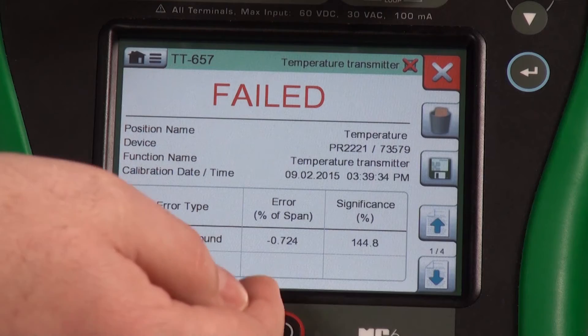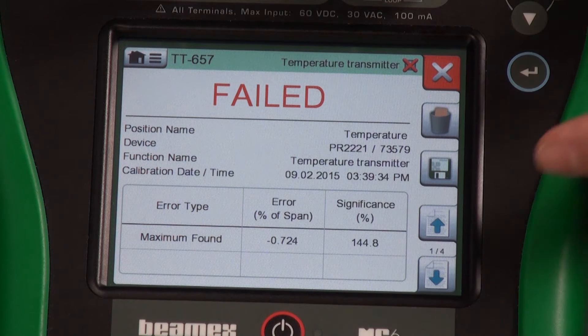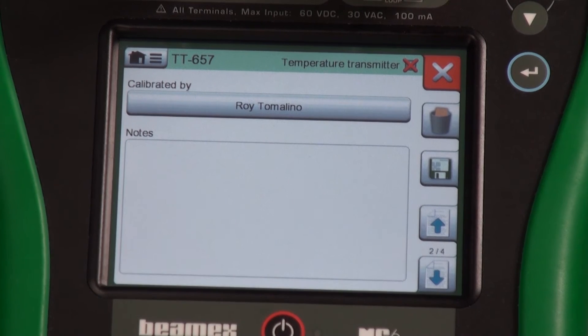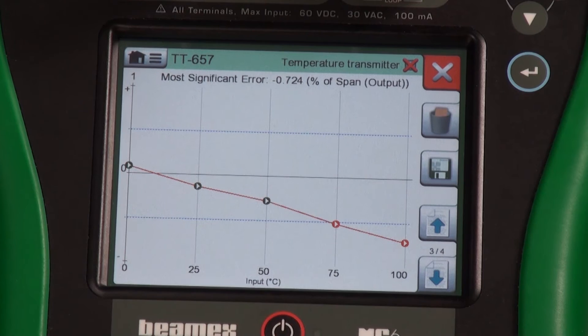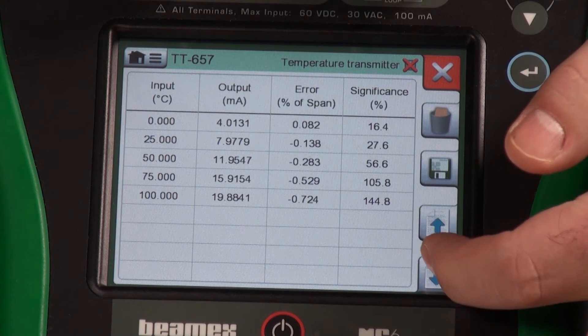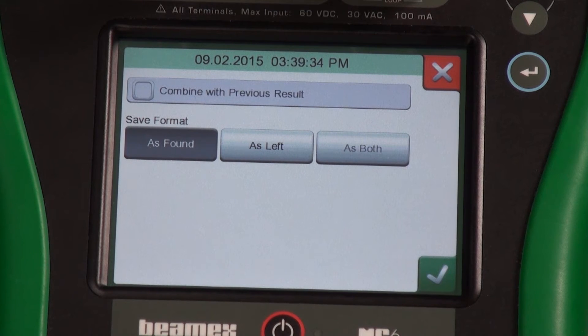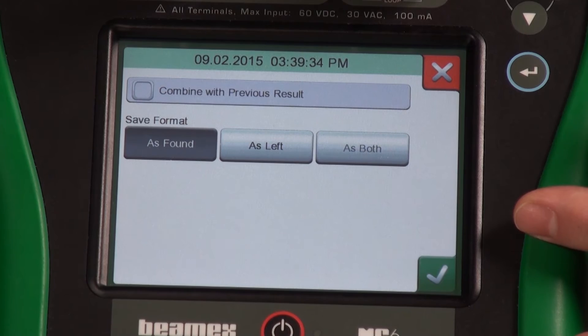Now that we've reached the end of our test, we can see our full error — negative 0.724 percent at the bottom. Our original tolerance was half a percent, represented by those blue lines. Before we save, I can hit the down arrow to pick who did the calibration, and I could put any calibration notes. The graph shows it was passing for the first three test points, and in the final two we went below in a negative direction. I can see the exact error at each test point on the final page. Now let me hit save — we have an option to save as found, and I'll press the check mark. We've captured our as-found results and we know that it's failed, so we need to make an adjustment and then do an as-left test.